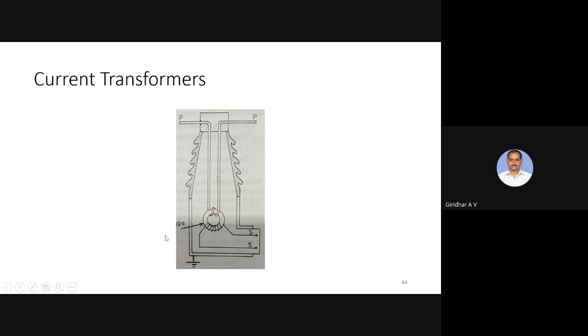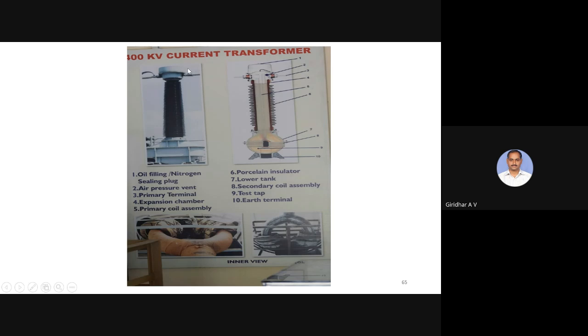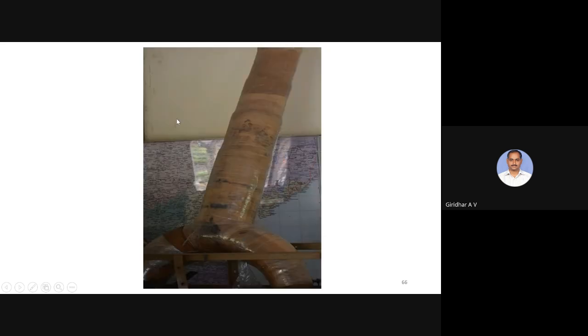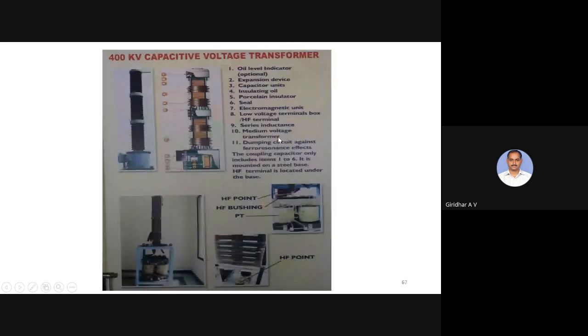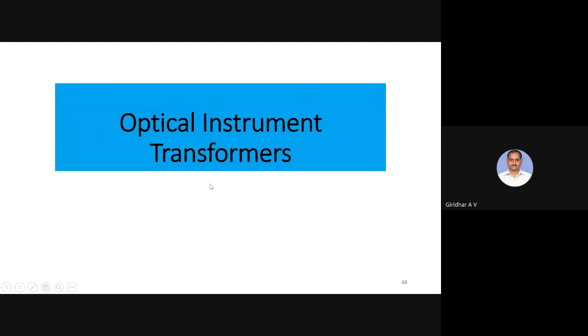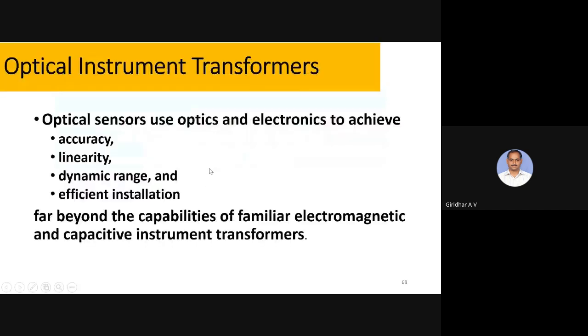So this is a current transformer, where we transform from high current to low current. You can see these current transformer designs, a typical current transformer. These are the capacitive voltage transformers. Even nowadays there are more advances in instrument transformers, like optical instrument transformers. They are used for accuracy, linearity, high dynamic range, and efficient installations.